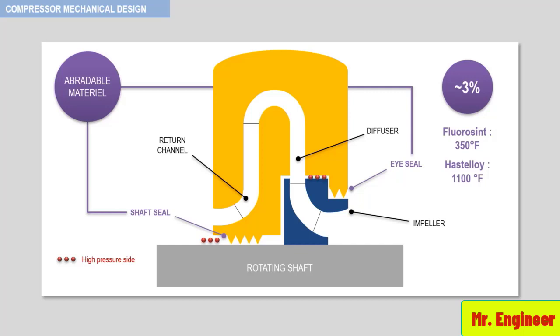Pressure balance is easily achieved by ensuring that the pressure behind the seals, as seen here, is less than or equal to the pressure between the labyrinth surface and rotor surface.